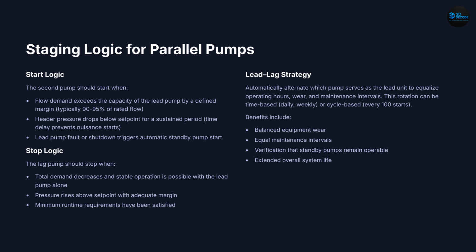Slide 11. Staging logic. In parallel systems, proper start and stop logic is critical. Pumps start when demand exceeds capacity and stop when demand reduces. Lead lag control ensures equal usage of pumps and improves reliability.